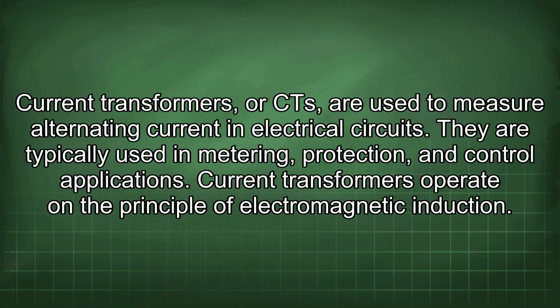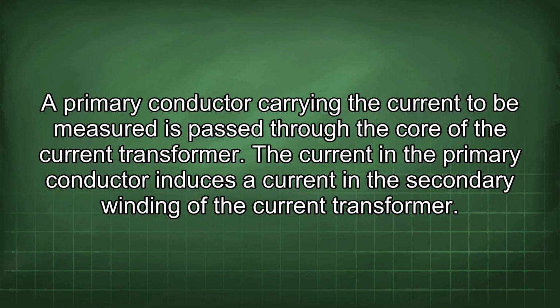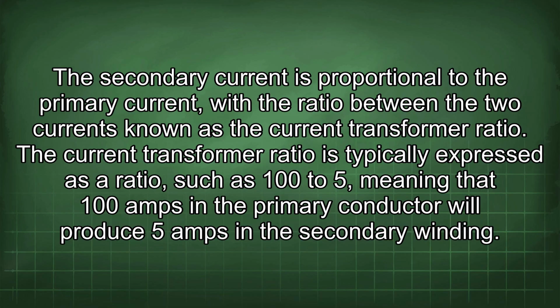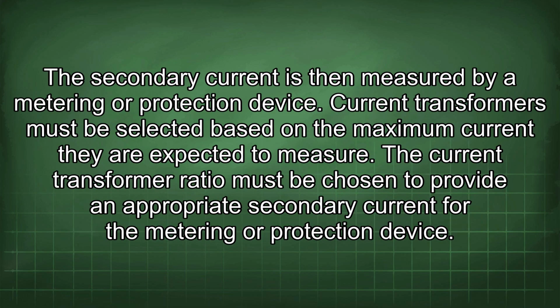Current transformers operate on the principle of electromagnetic induction. A primary conductor carrying the current to be measured is passed through the core of the current transformer. The current in the primary conductor induces a current in the secondary winding of the current transformer. The secondary current is proportional to the primary current, with the ratio between the two currents known as the current transformer ratio. The current transformer ratio is typically expressed as a ratio such as 100 to 5, meaning that 100 amps in the primary conductor will produce 5 amps in the secondary winding. The secondary current is then measured by a metering or protection device.